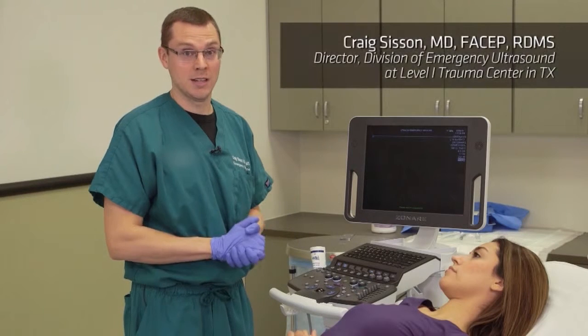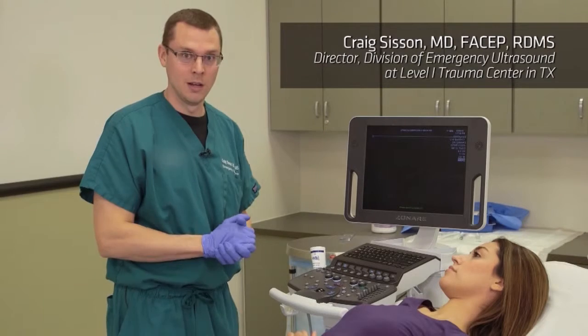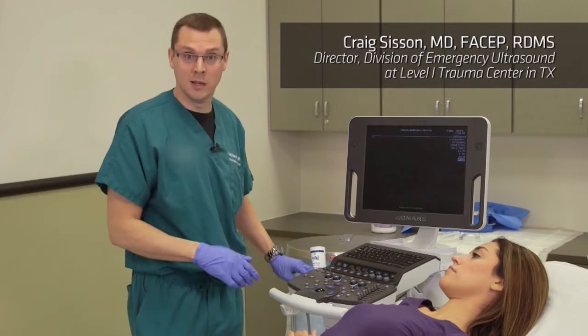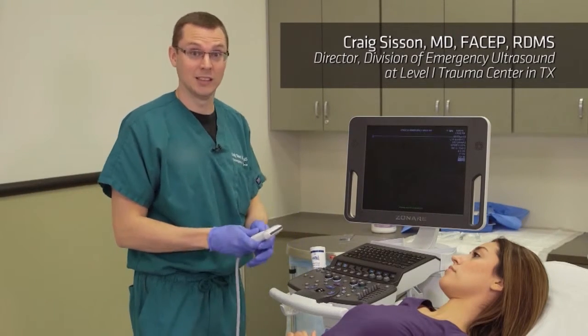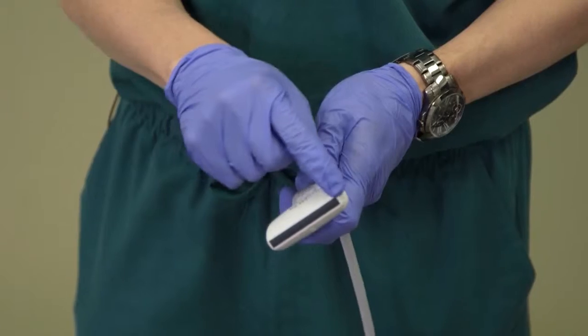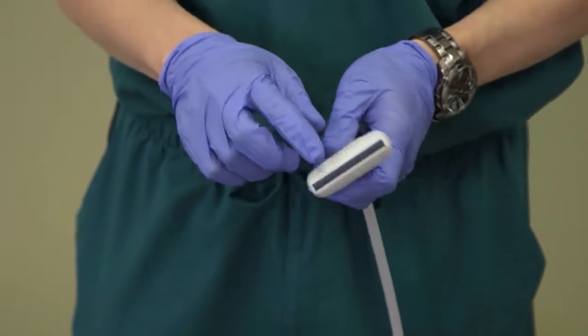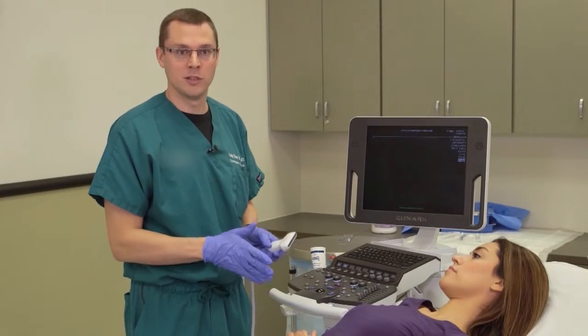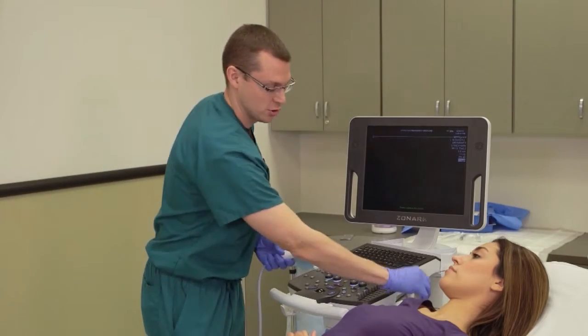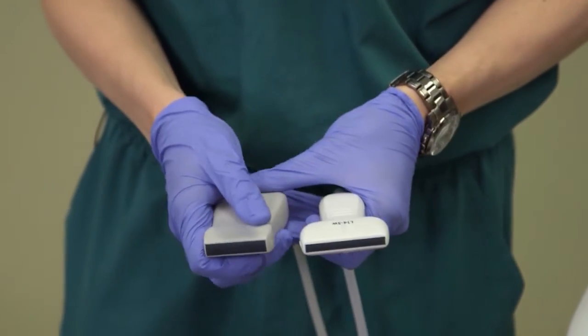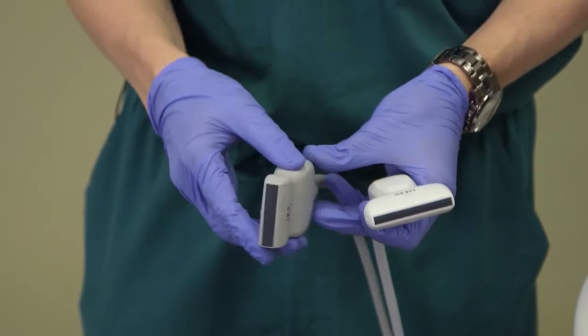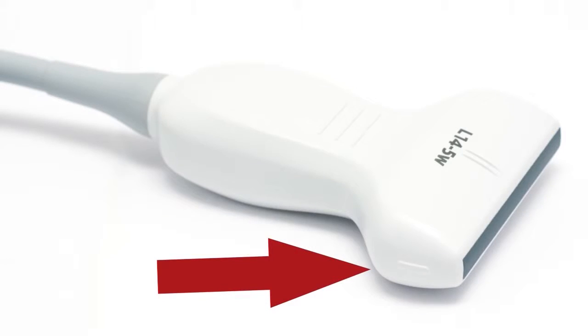So the first thing we're going to discuss is transducer selection. As for this particular exam, the ocular examination, you want a linear transducer. That's one that has a flat footprint that goes onto the patient. There are a couple of different Zonare linear transducers you can choose from, which have variable sizes in the footprint that will actually contact the patient. Each one has a marker on one side, the probe marker, that gives you orientation during the examination.